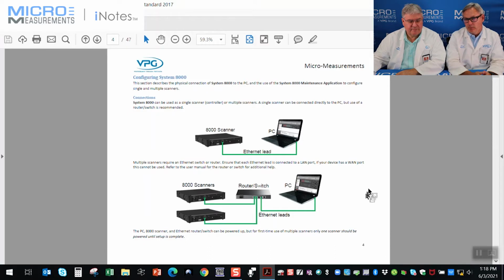One of the most important things to recognize here is that if you're going to connect just from the scanner to your computer, that's perfectly fine, but you need to be using a crossover cable, or two straight cables in a crossover box. So if your intent is to go straight from scanner into PC, you need to have that crossover cable or that small crossover box in place in order for it to work properly.